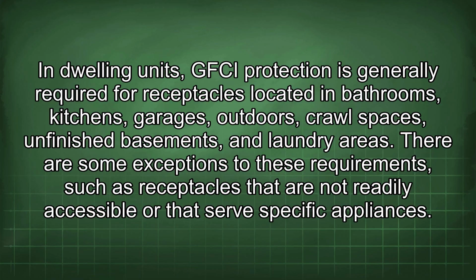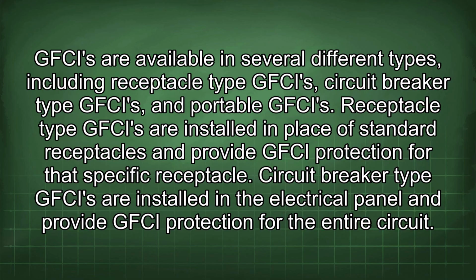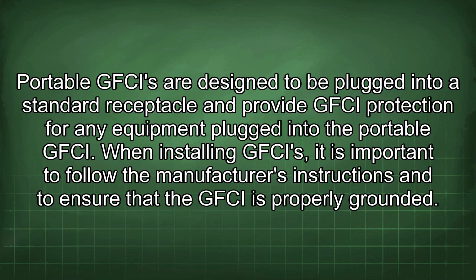GFCIs are available in several different types, including receptacle-type GFCIs, circuit breaker-type GFCIs, and portable GFCIs. Receptacle-type GFCIs are installed in place of standard receptacles and provide GFCI protection for the specific receptacle. Circuit breaker-type GFCIs are installed in the electrical panel and provide GFCI protection for the entire circuit. Portable GFCIs are designed to be plugged into a standard receptacle and provide GFCI protection for any equipment plugged into the portable GFCI.